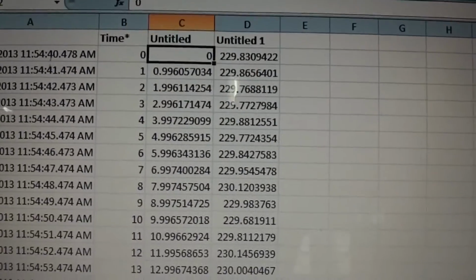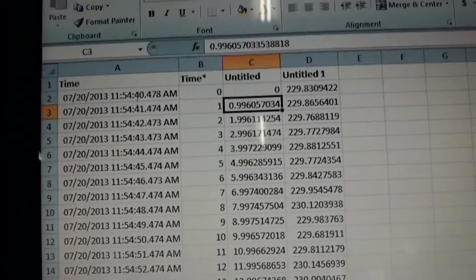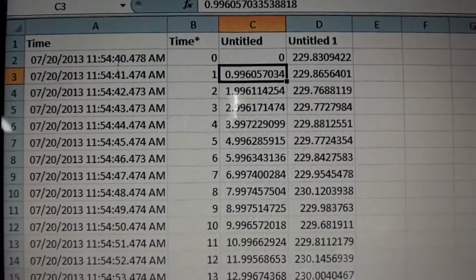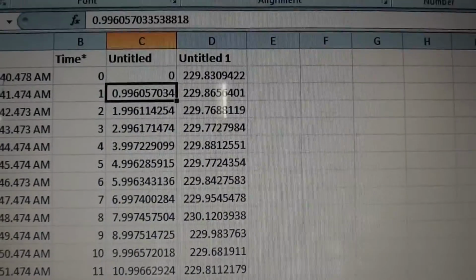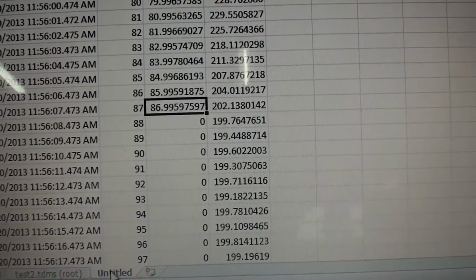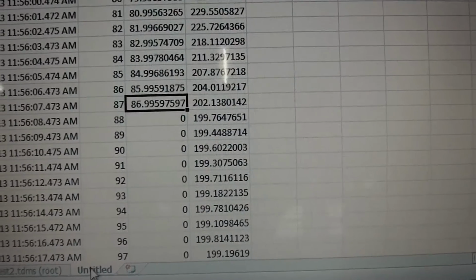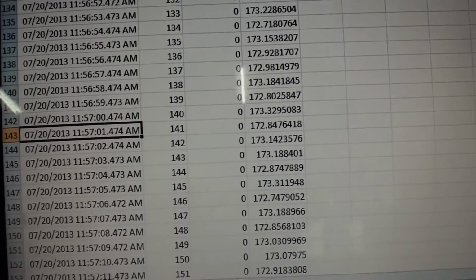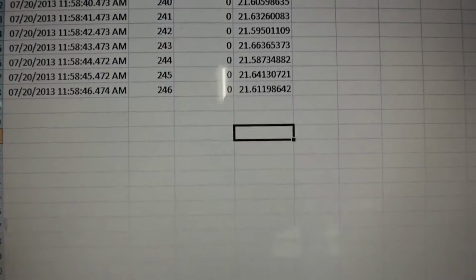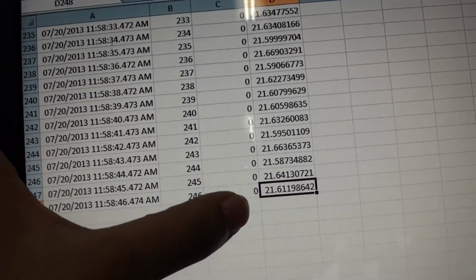So, similarly, we have for the swell part of it as well. As we can see, the value of the voltage is 229 volts, which is much greater than 207. So this event classifies as a voltage swell. And so at the start of the program, that was at 11:54 a.m., we had created a voltage swell just for demonstration, and the voltage has swelled for about 1 second, 2 seconds, 3 seconds, etc. And as we go further below, now the voltage has come down to below 207 volts. So we are able to see that a voltage sag has occurred. And as we go further below, if the value of the voltage changes further, here we see that the value of the voltage has come to 21 volts. And since that's an interruption, the swell duration column has become 0, and it displays a 0 value.